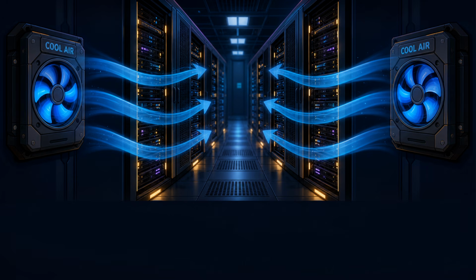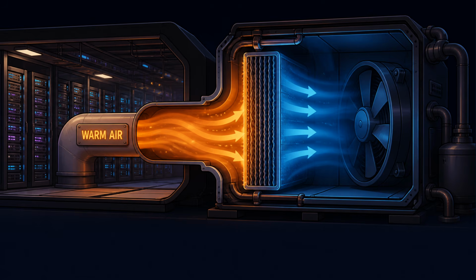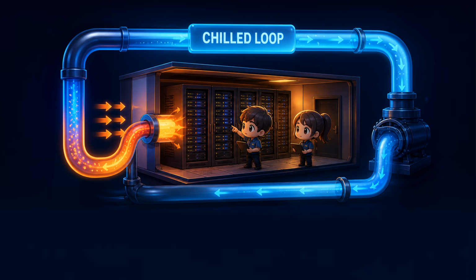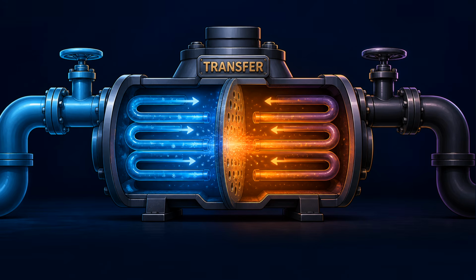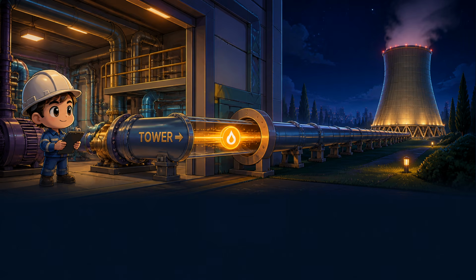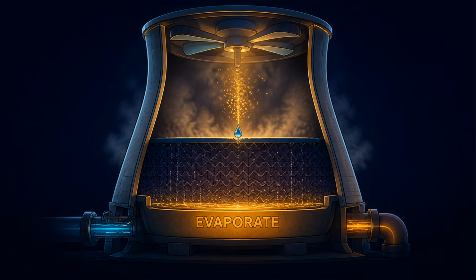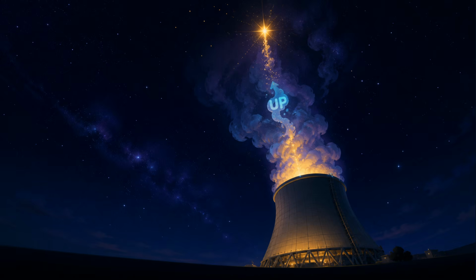Fans move cool air toward the computers. The warm air leaving the racks passes through cooling equipment. In one common design, that heat moves into a chilled water loop. A chiller transfers it again into a condenser water loop. The condenser water carries the heat to a cooling tower outside. Inside the tower, a small portion of water evaporates, carrying heat into the atmosphere.